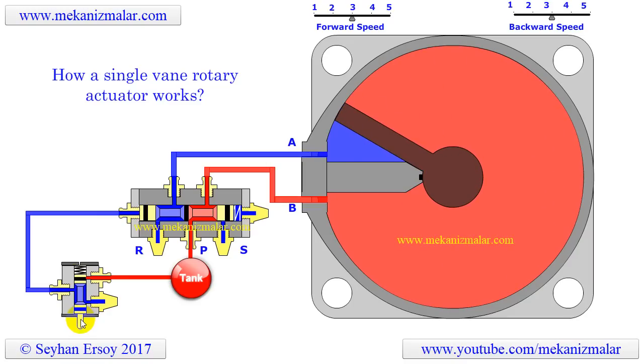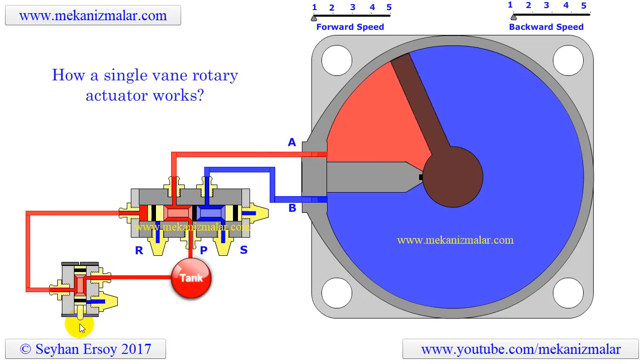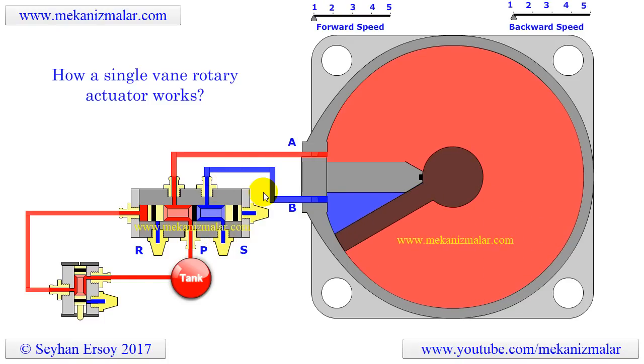However, as long as the design allows, you can produce any angle in the range of 0 to 360 degrees. In this video, the vane makes a 300-degree rotation. When the high-pressure flow coming from the four-way valve is connected to port A of the rotary actuator, port B releases low-pressure oil to the tank. This causes the actuator to rotate in a clockwise direction, as shown in the animation.